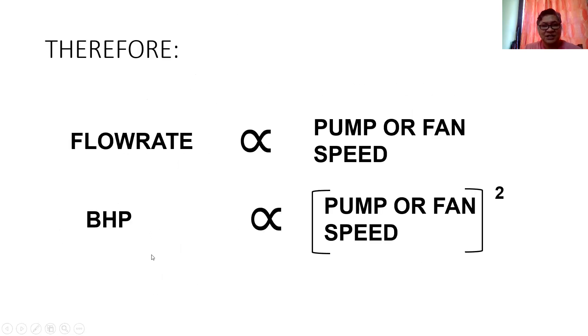By this function, we can say that flow rate is directly proportional to pump or fan speed. The brake power is directly proportional to the cube of the pump or fan speed.